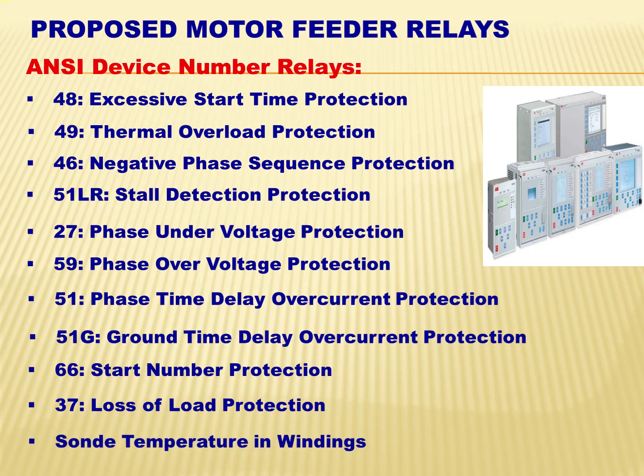Okay? Last will be the sonde temperature in windings. Resistance temperature detectors, for example, the 100 ohm platinum elements or thermocouples, are usually embedded in the 3 stator phase windings to detect overheating in the vicinity of conductors.